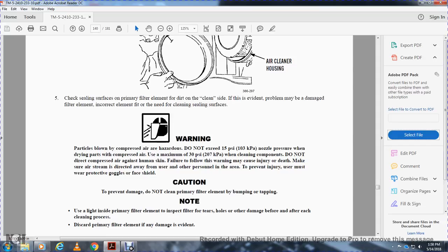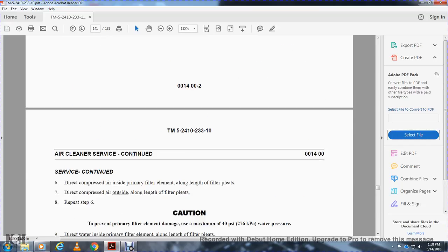Do not clean the primary filter element by pounding or tapping. Note: use a light inside the primary filter to inspect for tears, holes, and other damage before or after each cleaning process. Discard the primary filter element if any damage is evident. Service continued. Direct compressed air inside the primary air filter element along the length of the filter pleats. Direct compressed air outside along the length of the filter pleats.